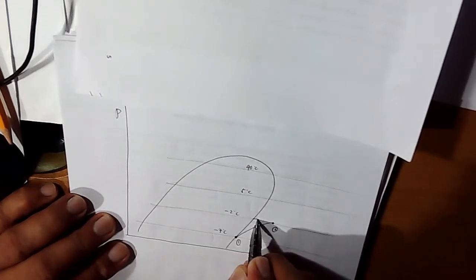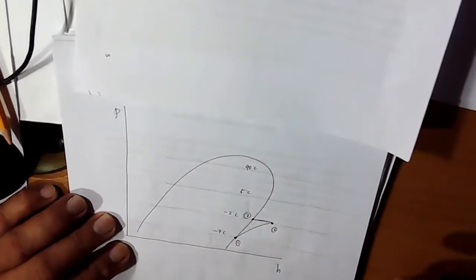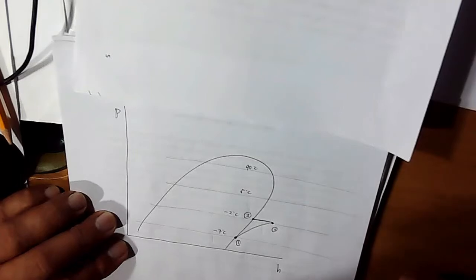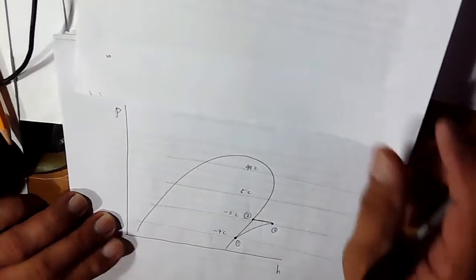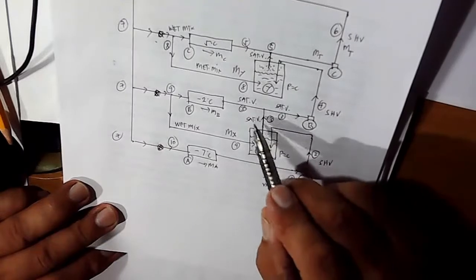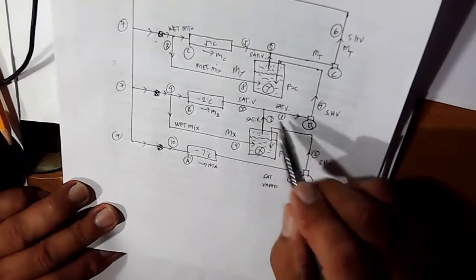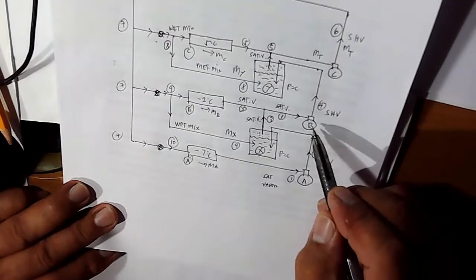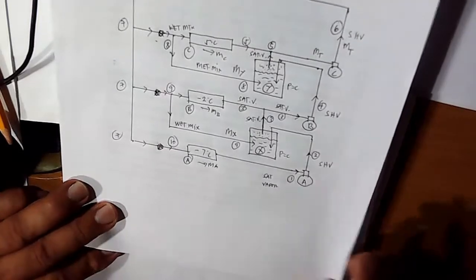Okay, so from superheated vapor, once again change into saturated vapor corresponding to this pressure line. So that is your point 3. That is one function of your intercooler: change superheated vapor into saturated vapor. Okay. And then at point 3, all of these with the same saturated vapor condition will enter compressor B. And then you compress that into 4 to convert that once again to superheated vapor.